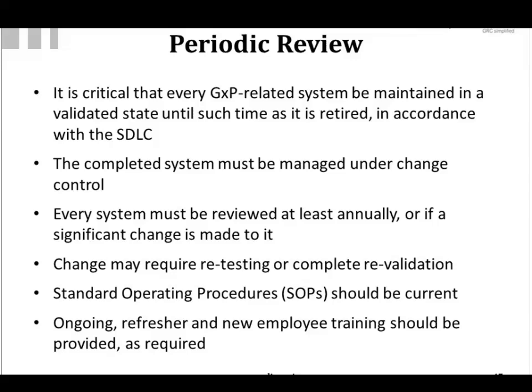The periodic review itself should be documented in a report that says when you did it, what you looked at, why you did any kind of retesting you might have done, or why you recommended no retesting is required, your rationale for that, and then a summary.